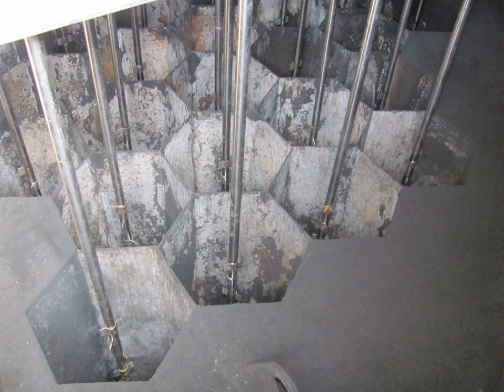If injection of ammonium sulfate occurs at a temperature greater than about 600 degrees Fahrenheit, 320 degrees Celsius, dissociation into ammonia and sulfur trioxide results. Depending on the ash, SO3 may preferentially interact with fly ash as SO3 conditioning. The remainder recombines with ammonia to add to the space charge as well as increase cohesiveness of the ash. More recently, it has been recognized that a major reason for loss of efficiency of the electrostatic precipitator is due to particle buildup on the charging wires in addition to the collection plates, Davidson and McKinney, 1998. This is easily remedied by making sure that the wires themselves are cleaned at the same time that the collecting plates are cleaned.